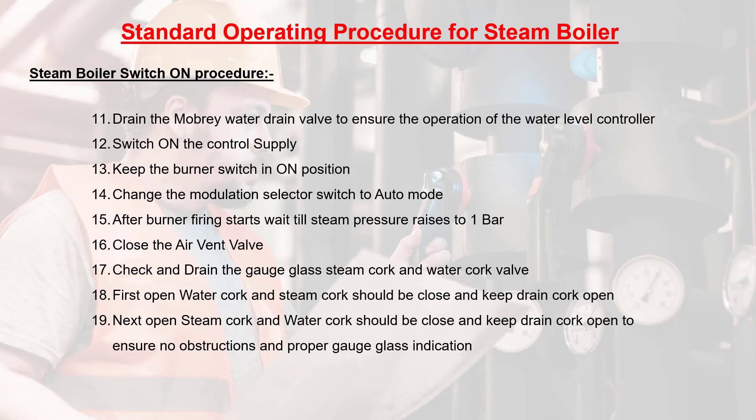Step 16: close the air vent valve. Step 17: check and drain the gauge glass steam cock and water cock valve. Step 18: first open the water cock with steam cock closed and keep drain cock open. Step 19: next open the steam cock with water cock closed and keep drain cock open, to ensure no obstructions and proper gauge glass indication.